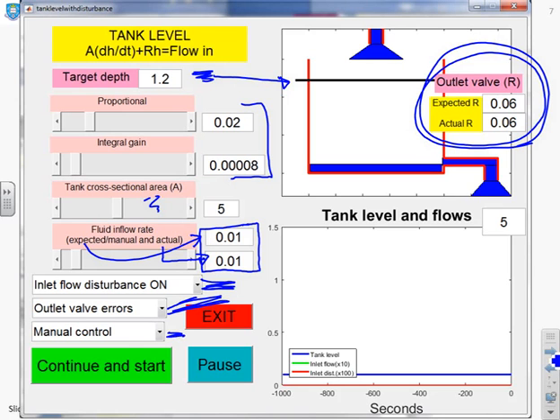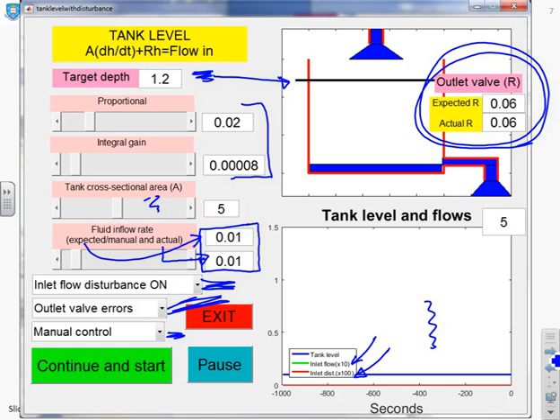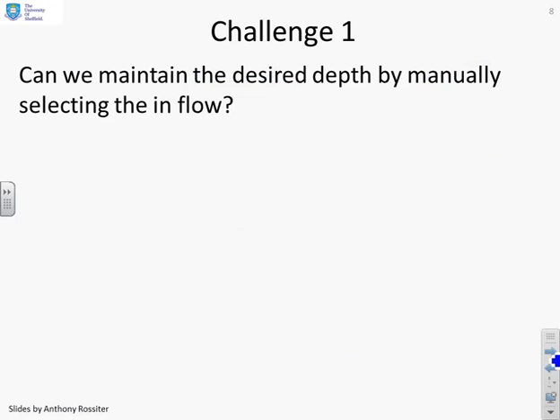Finally, the final pop-up allows you to do manual control, it allows you to tune the PI, or in fact allows you to do a heuristic PI as well, where it's tuned for you. And all the plots are put down in this window, and you'll see the inlet flow in green and the inlet disturbance in red. So you can see whenever there's a spillage or something else, that red line will change, and it can only be positive.